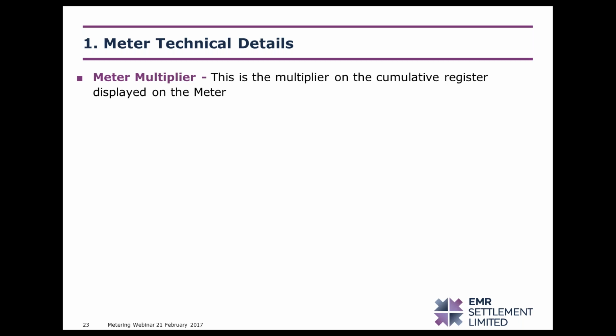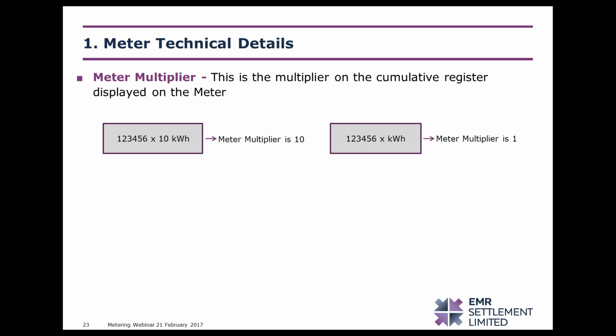The meter multiplier is related to the physical display on the meter. This is for the cumulative energy register. Some modern meters are limited to the number of characters they can have in this display, so this could be limited to 6 characters. And to prevent the reading going round the clock in too short a period of time, some meter manufacturers use a multiplier technique to prevent this from happening. The multiplier will be displayed on the display of the meter. So in the example on the left, the meter multiplier is 10 because there is a times 10 kilowatt hour multiplier applied to the display.